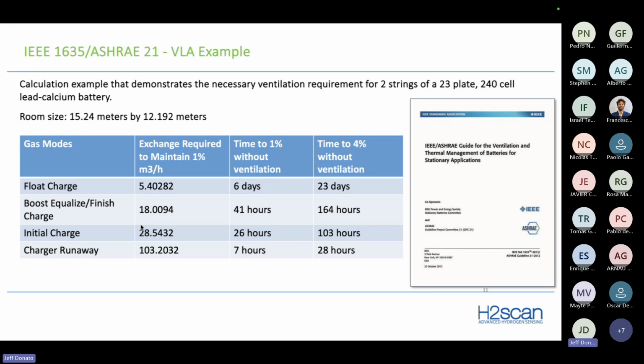This is an example of a real data center room. I'll tell you, it was a ticketing center for a very large theme park, and this is in South Carolina. They had 2 strings of 23 plate batteries, 240 cells, lead calcium batteries. The room size was only 15 meters by 12 meters.